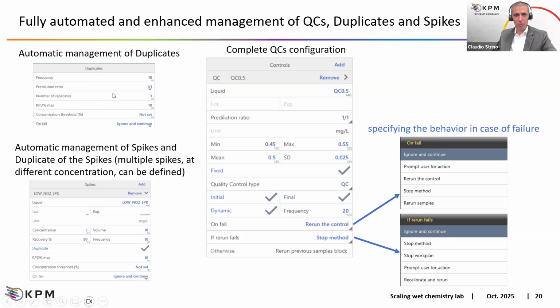Those two controls are very important, because on normal QCs we are just preparing type 2 water, adding the molecules of interest for the analyte, and running it. But with the duplicate and spike, we can also check the repeatability and the accuracy of the instrument on the real sample matrices. So we can check the repeatability by running the duplicates and monitoring the RPD percentage. We can automate the spike to check the accuracy of the instrument in performing the spiking, and we can automatically control the recovery percentage. And moreover, by running the duplicate of the spike, we can check the repeatability of the instrument in performing two subsequent spikings. And we can define multiple spikes for each method. So low, medium, high spike.